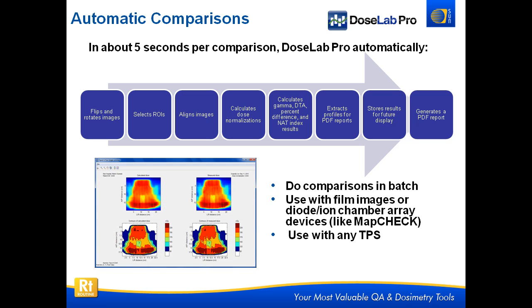Another nice thing is that we can actually do comparisons in batch. If we do one comparison automatically in five seconds and we have an 11-field IMRT QA, we can put all 11 fields in there, do them all one by one in batch, and be done in about one minute with a PDF report ready to import to our R&V system. This works with film, MapCHECK, matrix, and PTW-729 — really just about any way you can measure dose is compatible with DoseLab.